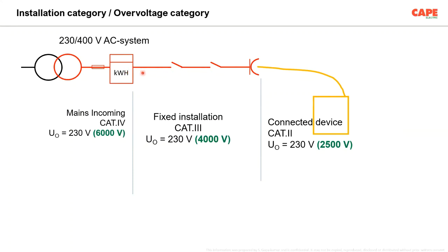say for example, your main distribution board, your cables, your sub distribution board, your switch, socket, your light fittings, your fan. These are fixed electrical installation. So all the fixed electrical installation up to the socket, for the purpose of equipment safety, we are talking about equipment safety, the equipment used in the fixed installation must be of category 3. Means a 230 volt equipment must be able to withstand up to 4 kV voltage impulse. Voltage impulse is nothing but surge voltage. It is a classified example of testing. Once we go further into the next 2-3 slides, you will be able to understand what I am talking about.